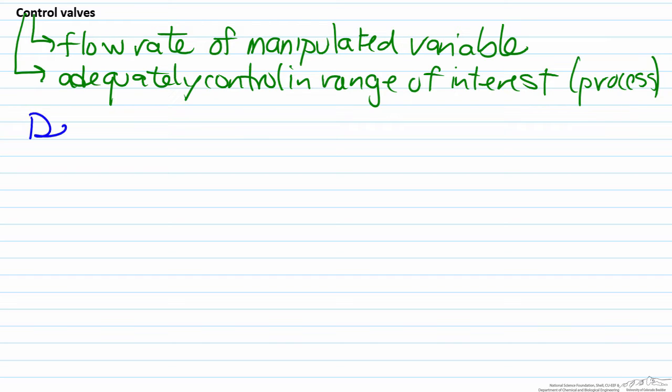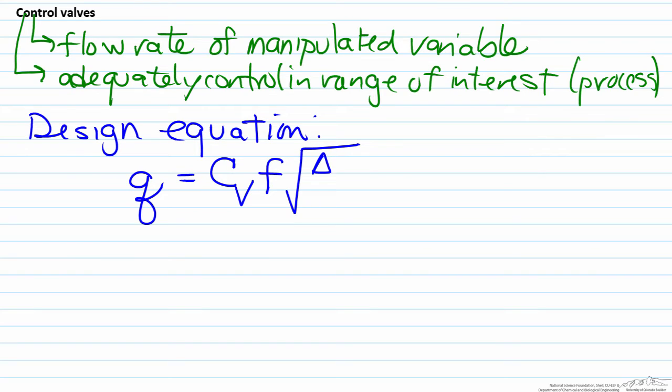The design equation for the control valve can be represented by the following relationship, where Q equals CV multiplied by F multiplied by the square root of delta P over Gs. Now let's go through what each of these variables represents. Q represents the flow rate of whatever fluid you have.